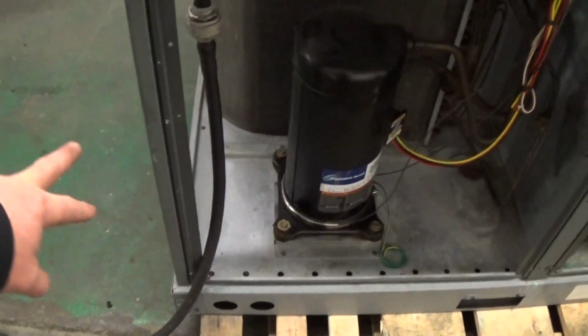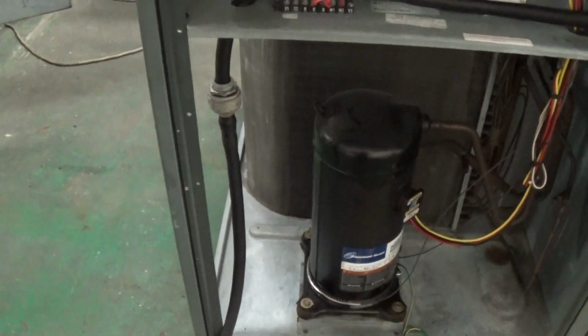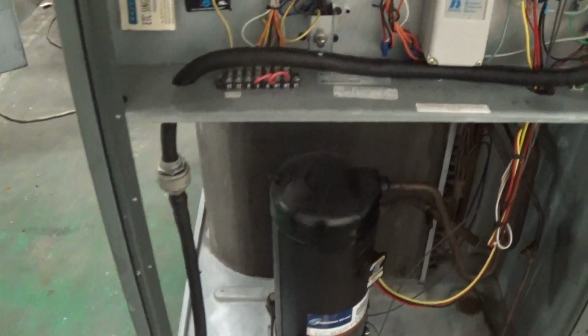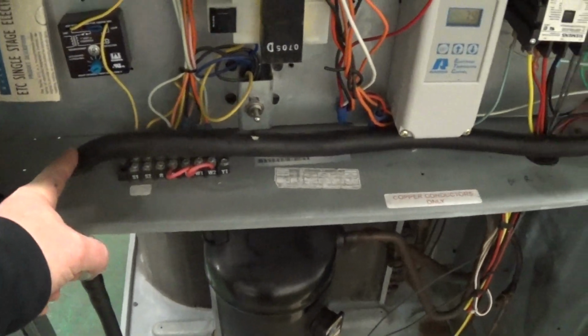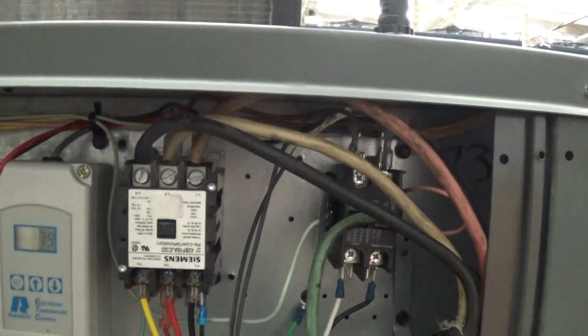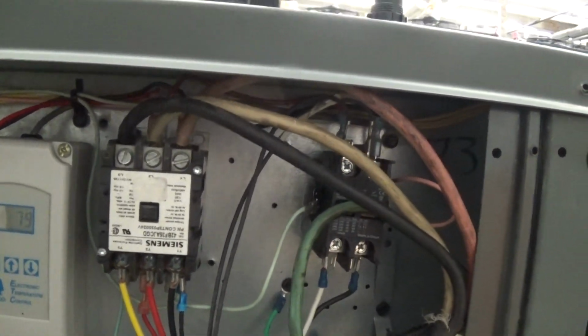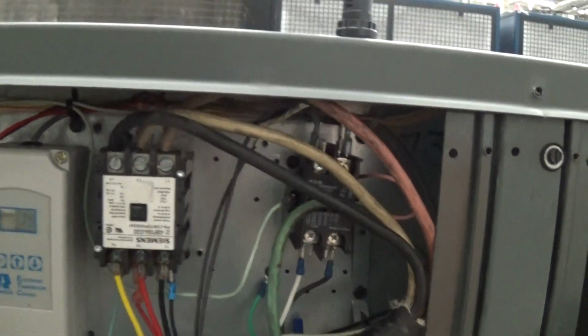So this is 208, 230, 3-phase. Your incoming power, you can come through any one of the panels that's ultimately on the chiller, and most people will come up through here and just come right up to the top of that primary contactor with your 3 hots, and then your ground is right here.